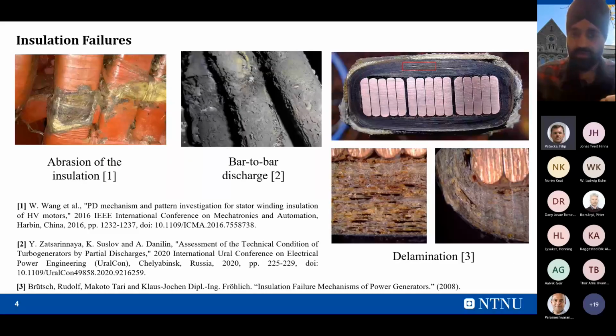I'll show some pictures of how these failures occur, as there are several failure reasons. Insulation failure is not because of one particular reason. There are multiple types of stresses, and they take place in a synergistic way, a simultaneous combination of several different effects: thermal, electrical and mechanical. So it's not a single effect that leads to the damage of the insulation. These are some gaps near the copper strips and inside the insulation.